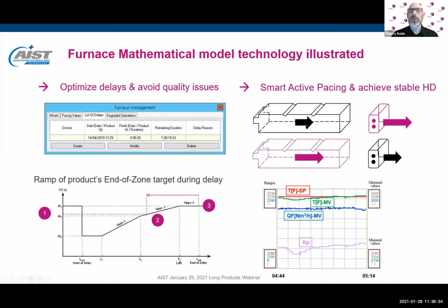The active pacing will help you increase productivity, for example, without affecting quality. But for that you also need to achieve stable heat demand. For that, we have fuzzy logic functions that provide PID settings to the level 1 heat demand management, to have a very stable temperature in the furnace and a very stable gas flow distribution all along the control.